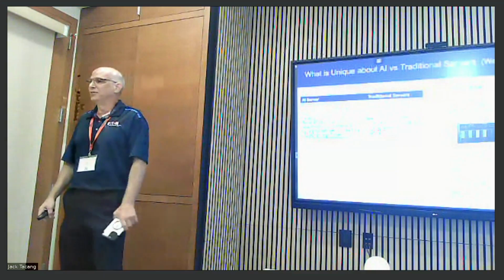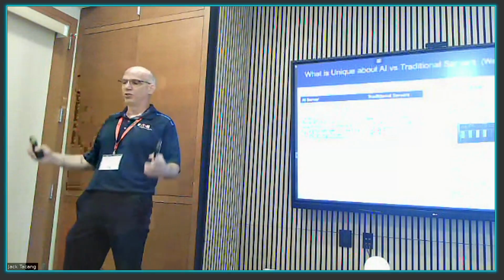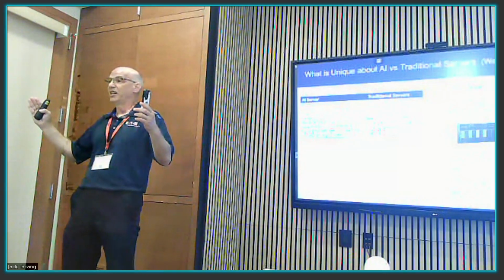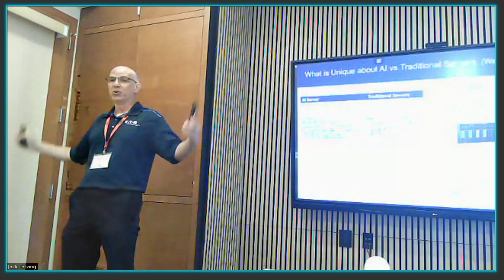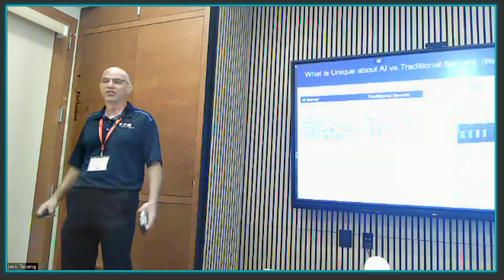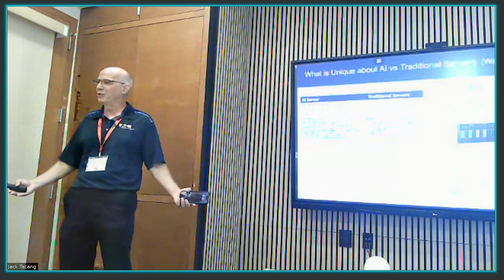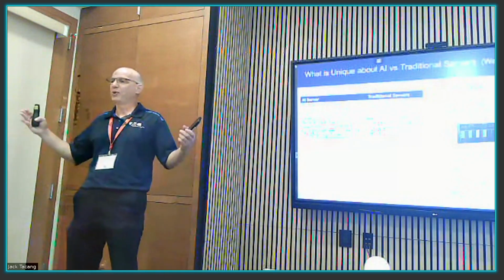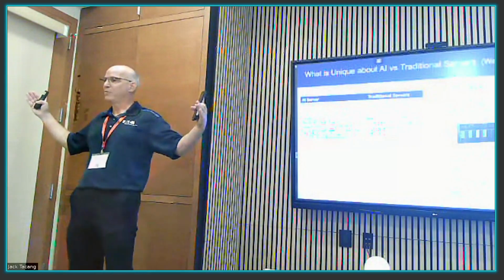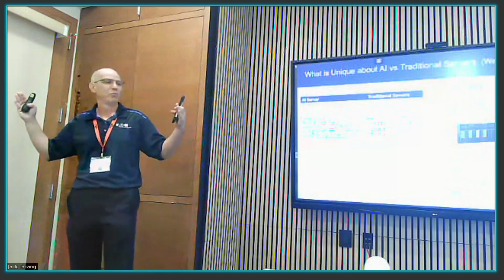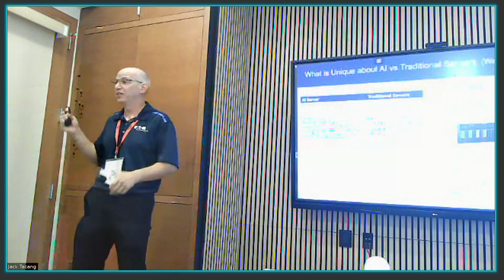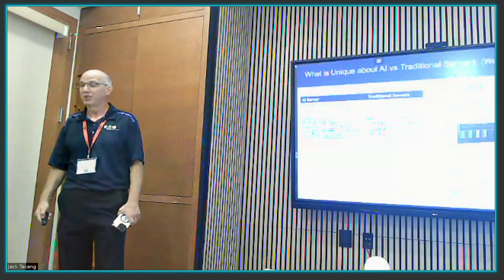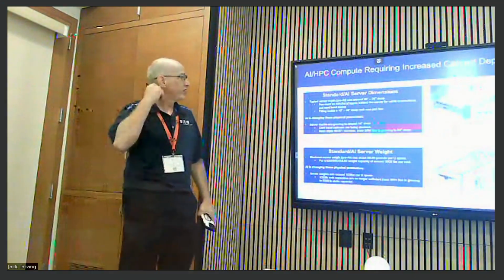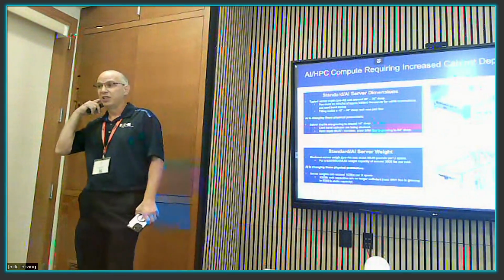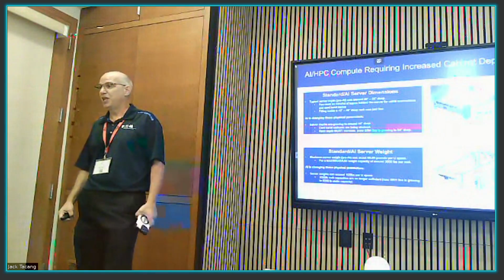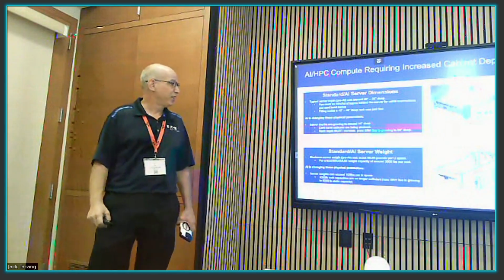But what about depth? The standard depth on a traditional server is usually about 30 inches. On an AI server, they're going beyond 40 inches. Most of the cabinets out there today are 42 and 48 inches deep. I can't fit an AI server in a traditional cabinet. Even if the server is 42 inches deep and I have a 48-inch cabinet, there's no room for any infrastructure. I can't put the cabling, the PDUs, or, in the case of an AI server, the liquid manifold in the back. It's not going to work. So we've introduced a brand new cabinet, released a couple of days ago, a 54-inch cabinet, to be able to meet the needs of AI.